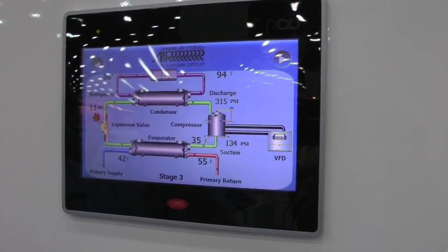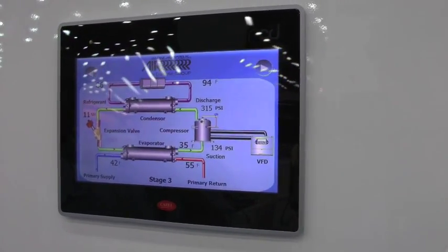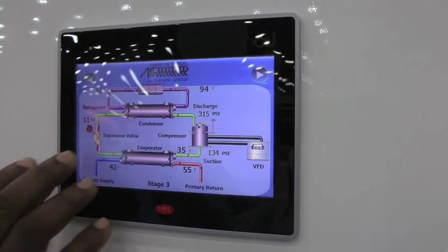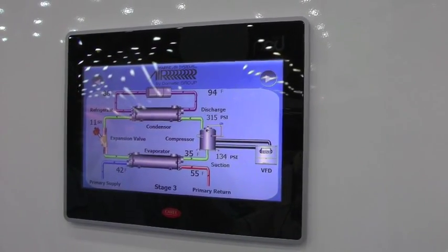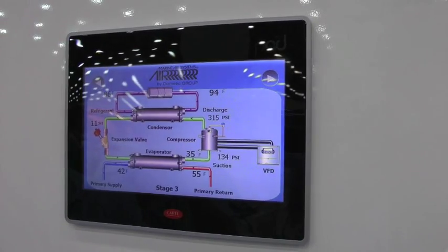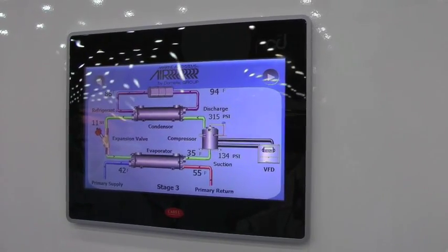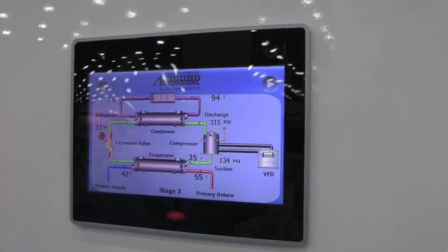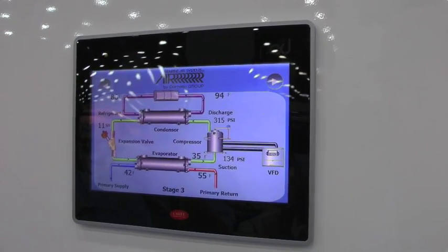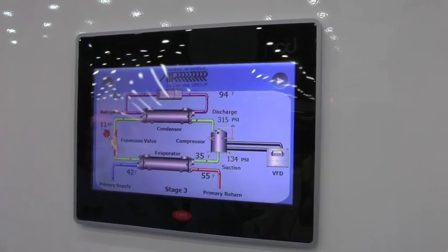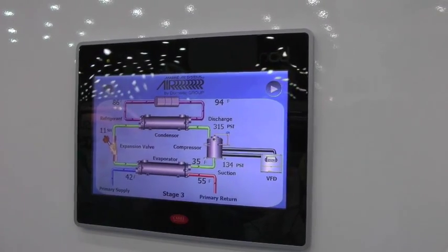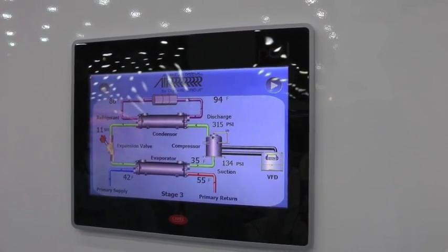With this, the real-time refrigerant circuit is also reporting your superheat value, which in the refrigeration world is important because that allows you to know how well your system is functioning, how much it's thermally loaded, and how well it's compensating and controlling the chill water loop.